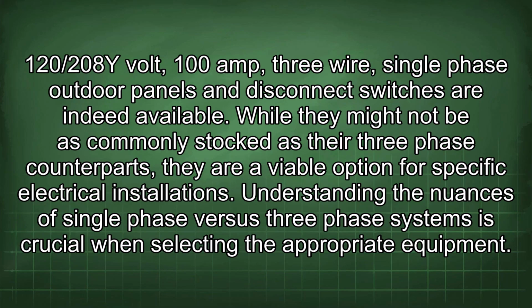120/208 volt, 100 amp, 3-wire, single-phase outdoor panels and disconnect switches are indeed available. While they might not be as commonly stocked as their 3-phase counterparts, they are a viable option for specific electrical installations. Understanding the nuances of single-phase versus 3-phase systems is crucial when selecting the appropriate equipment.